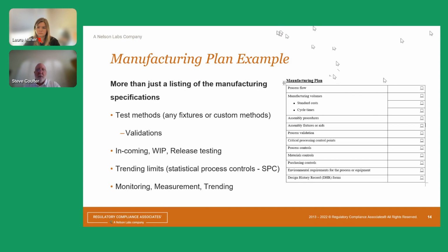And actually, if you want to see some of the details of this, they're back in that 21 CFR 820.181. It lists the key topic areas, not a detailed manufacturing plan, but the key topic areas that you need for each one of these. But some of the things you have to remember, because these are, in experience, sometimes missed.